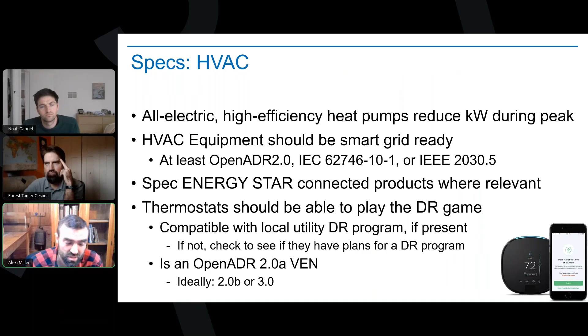In terms of how it's incorporated into models and what the modeled impact is to demand, it's a lot of getting in and adjusting set points during peak periods. Understanding the overall building peak and utility peak, and looking at how shifting temperature set points at that specific point in time, or over a week, is going to impact things - what the zone temperatures will look like and how much they'll actually float. That's where passive strategies lend a lot more flexibility, giving a slower drift in temperature.